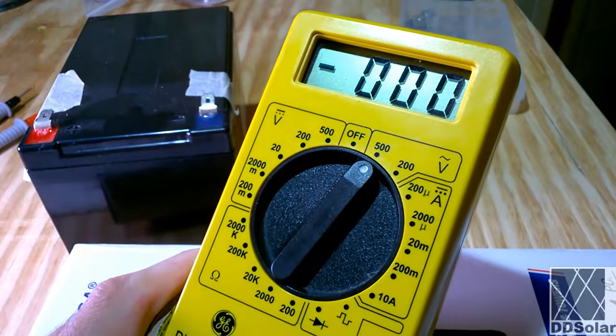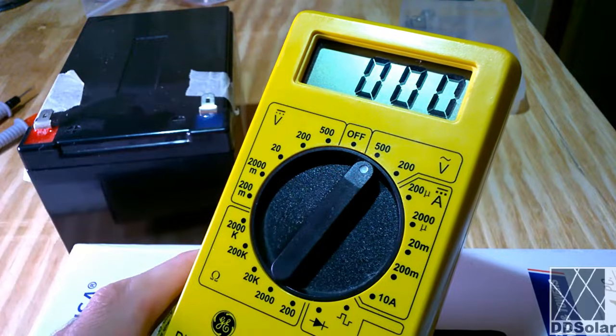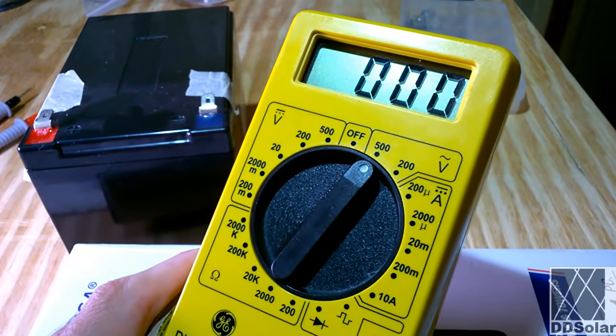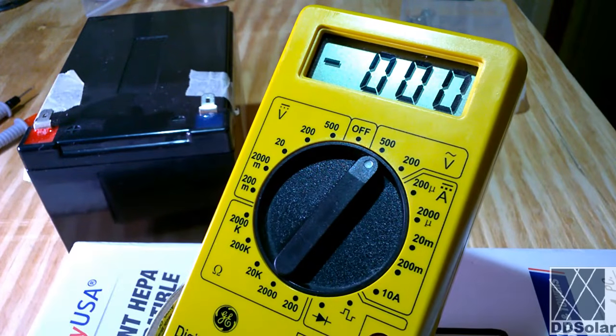I'm going to let the meter zero out. It's a good idea to give the meter 5 or 6 seconds to zero out and reach a zero, which is what this meter has done. If it's jumping around a lot or doesn't say zero, then there could be something wrong with the meter. You may have a bad battery, or you may need to just wait a while for it to settle down.